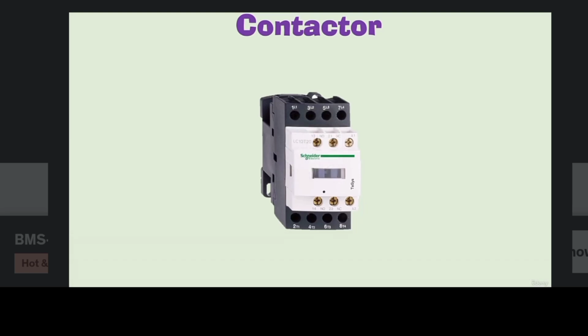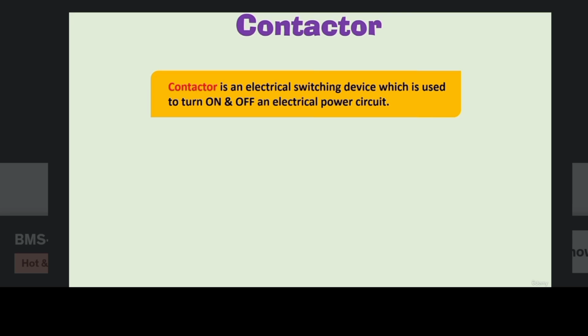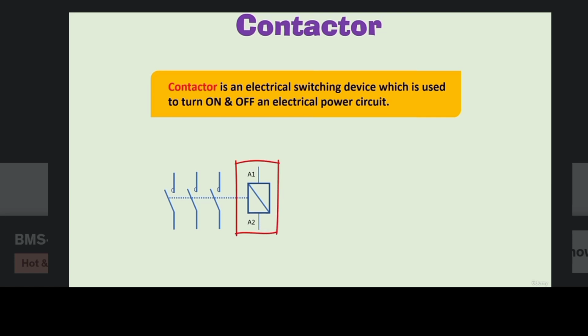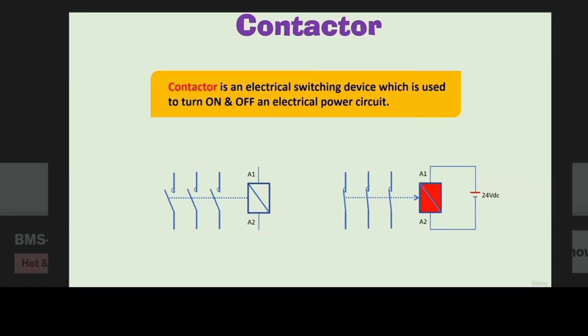In this video, we will talk about contactors. A contactor is an electrical switching device which is used to turn on and off an electrical power circuit. Here is a symbolic representation of a contactor. It works on the same principle as a relay. It has a coil where a control voltage is applied, and then it has switching contacts. When the contactor is energized, it pulls the movable contact, which closes the contacts, and the connected load is turned on.